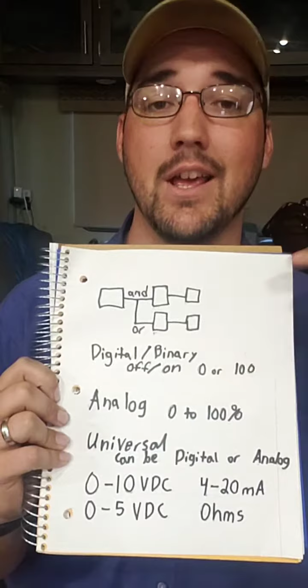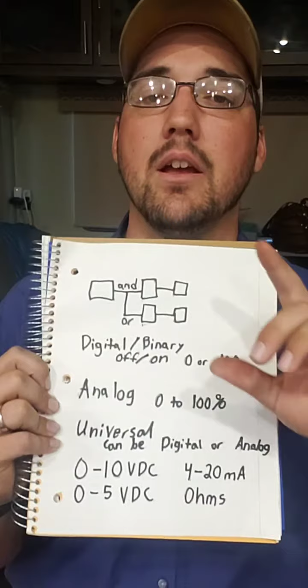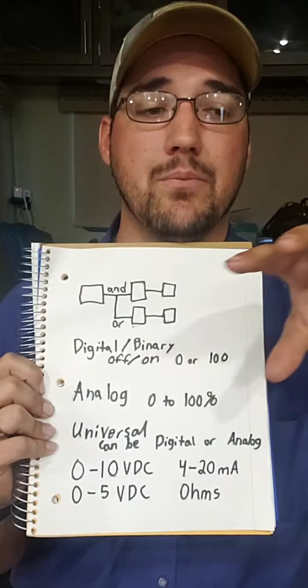Now, here's something I'm going to throw at you just to keep in mind. You can turn an analog output into a binary output. It has to be programmed into the logic, but if you need to turn something off or on, you would tell it, okay, you're either going to be 0% or you're going to be 100%. Don't give a range in between. You can tell your controller, your automation guy can, that if I don't want any signal coming out, it's going to be 0%. The moment I want signal, I'm not going to increase from 0 to 100. I'm going to go straight from 0 to 100% output out of that analog point.